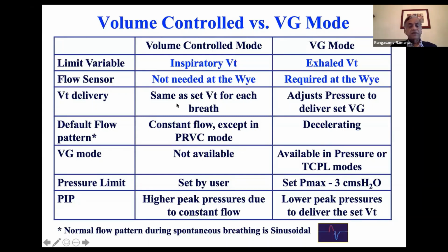Tidal volume delivery is the same as the set tidal volume for every breath in volume control mode, whereas in volume guarantee mode, the pressure is adjusted to get closer to the tidal volume you dialed in. So every breath doesn't get exactly the same tidal volume. But depending on the leaks, the ventilator will adjust the PIP by 3 to 5 centimeters to target the tidal volume that you ordered based on the previous breath. Default flow pattern is constant flow, except in the PRVC mode. Here is decelerating flow. I told you decelerating flow is better.